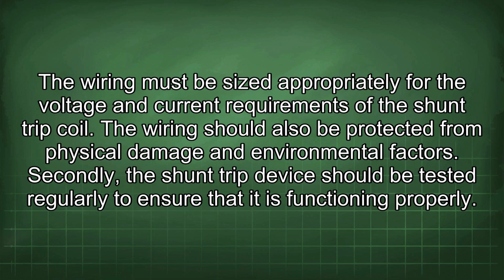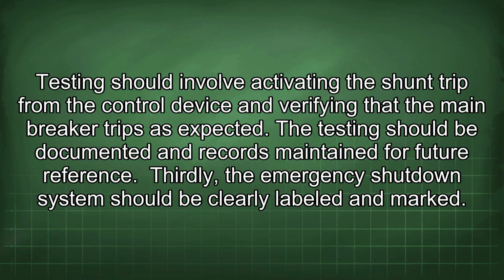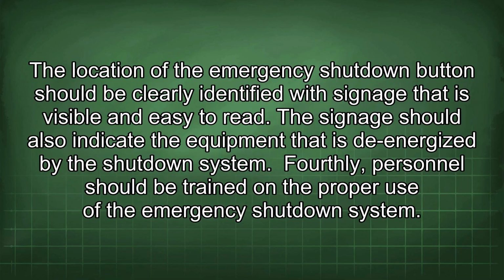Secondly, the shunt trip device should be tested regularly to ensure that it is functioning properly. Testing should involve activating the shunt trip from the control device and verifying that the main breaker trips as expected. The testing should be documented and records maintained for future reference. Thirdly, the emergency shutdown system should be clearly labeled and marked. The location of the emergency shutdown button should be clearly identified with signage that is visible and easy to read. The signage should also indicate the equipment that is de-energized by the shutdown system.